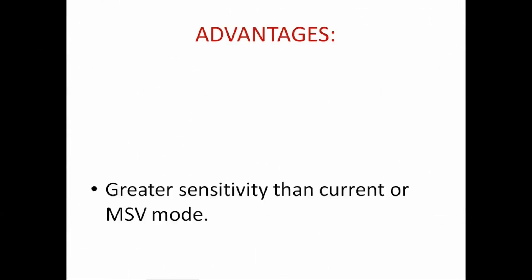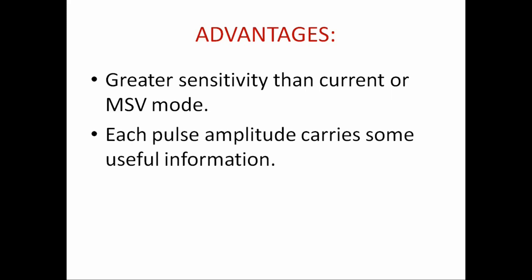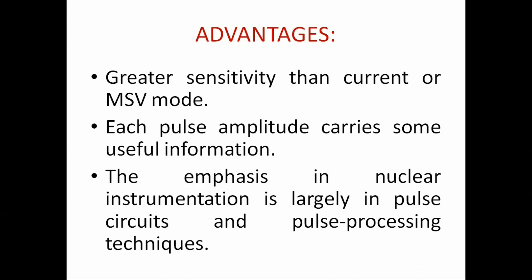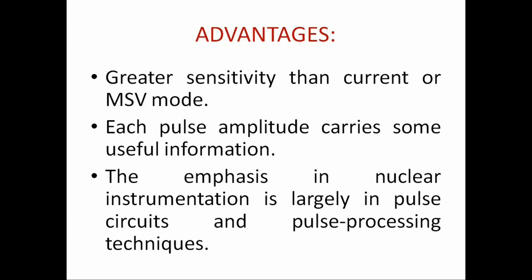Now let us look at a few advantages that the pulse mode of operation has to offer. First, the sensitivity achievable is often many factors greater than when using current or MSV mode, because each individual quantum of radiation can be detected as a distinct pulse. The second and more important advantage is that each pulse amplitude carries information that is often useful or even necessary for a particular application. In current and MSV mode this information on individual pulse amplitudes is completely lost, and all interactions regardless of their amplitude contribute to the average measured current. Because of these inherent advantages, the emphasis in nuclear instrumentation is largely on pulse circuits and pulse processing techniques.